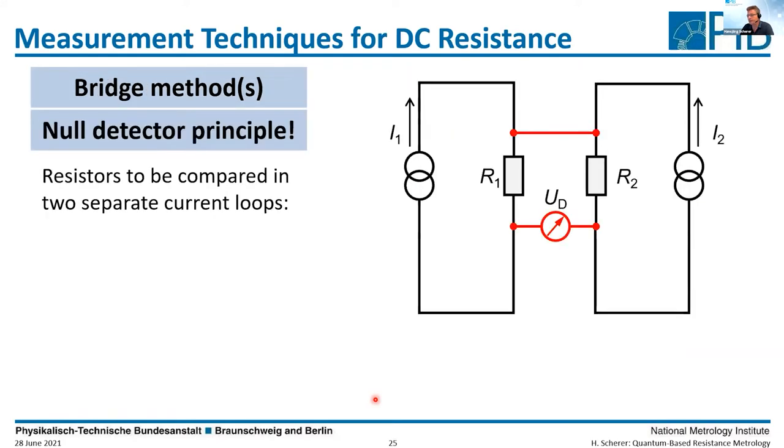So what is better is if you use a bridge method, as indicated here in principle. A bridge method means that you have two resistors, maybe one is the unknown and the other one is the known one, in two separate current circuits. So that means you feed individual currents to each resistor. Here you have two current sources.